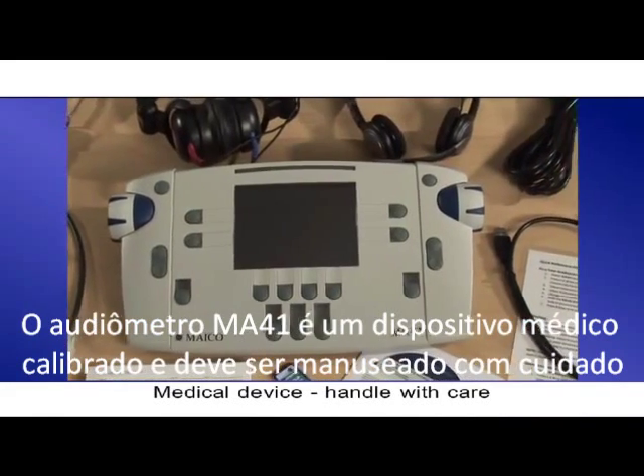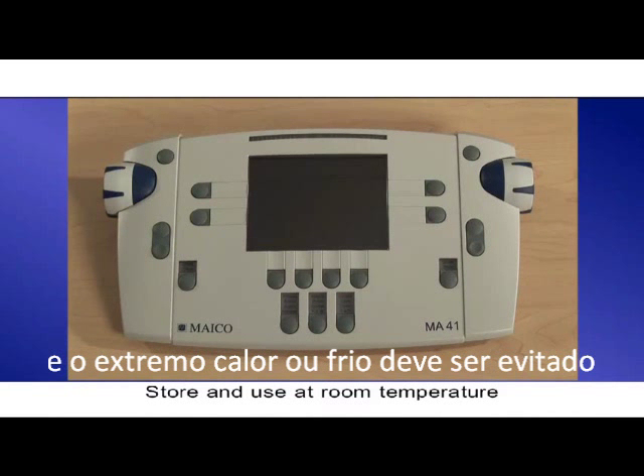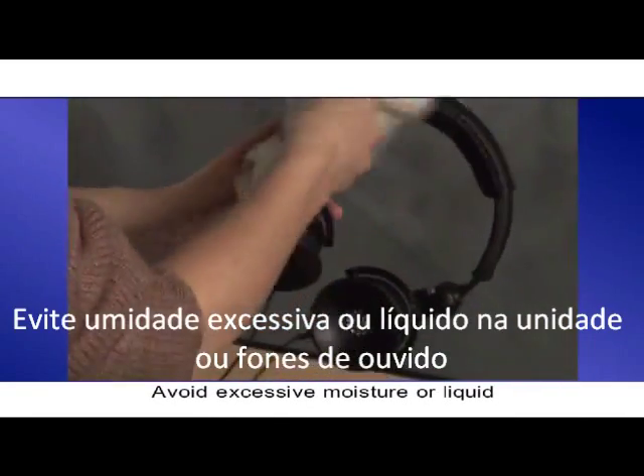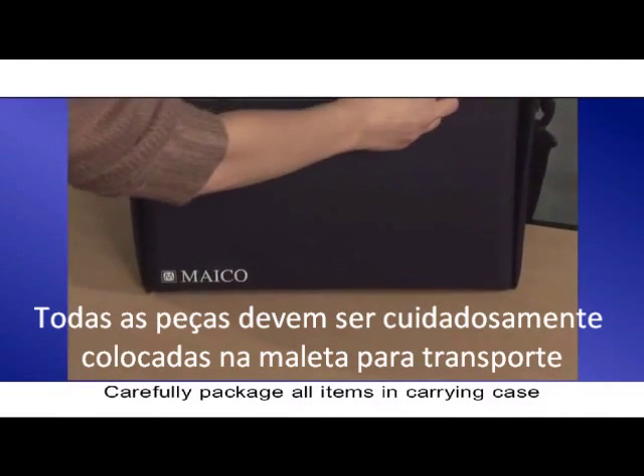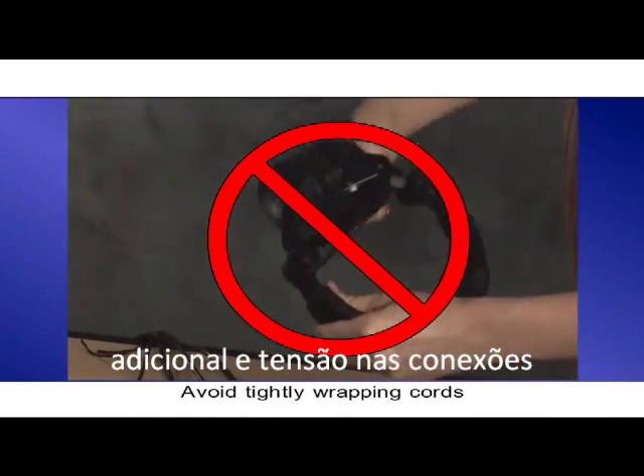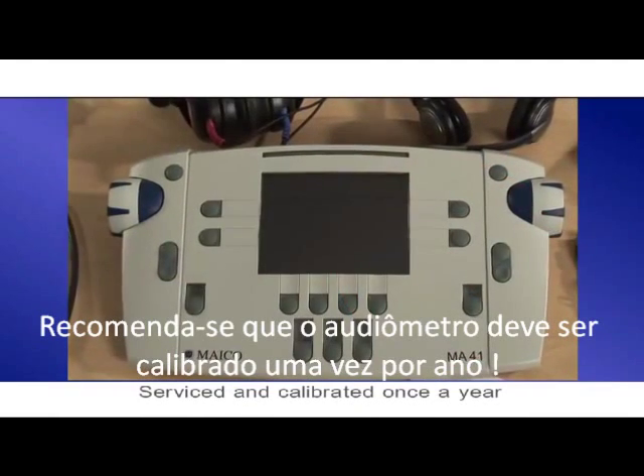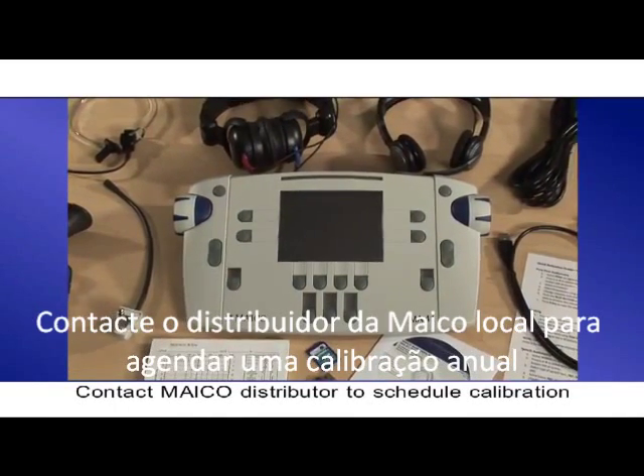The MA41 audiometer is a calibrated medical device and should be handled with care. The unit should be stored and used at room temperature, and extreme heat or cold should be avoided. The audiometer may be cleaned with a damp cloth or a disinfectant wipe. Please follow your facility's policy and recommendations for cleaning and disinfection. Avoid excessive moisture or liquid on the unit or headphones as this may damage the internal components. All pieces should be carefully placed in the carrying case for transport. When packing the unit, avoid tightly wrapping the cords as this will cause additional wear and tear. Never swap headphones without having the unit recalibrated, as the headset is specifically calibrated to the unit. It is recommended that the audiometer be serviced and calibrated once a year. Contact your local MAICO distributor to schedule an annual calibration.